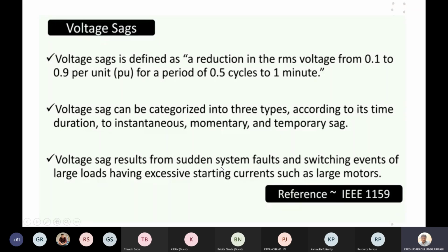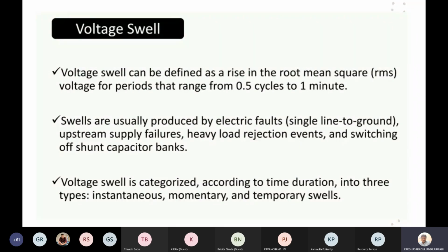Voltage sag results from sudden system faults and switching events of larger loads having excessive starting current, such as large motors. So if the voltage on the consumer side lies between 0.1 and 0.9 per unit of the rated voltage, and it lasts from 0.5 cycles to 1 minute, then it is said to be voltage sag. Whereas voltage swell can be defined as a rise in the root mean square voltage for periods that range from 0.5 cycles to 1 minute. Swells are usually produced by electric faults like LG faults, upstream supply failures, heavy load rejection events, and switching off shunt capacitor banks. Voltage swell is categorized according to time duration into three types: instantaneous, momentary, and temporary.